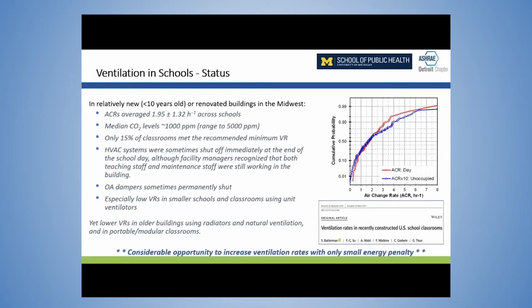So what's the status of ventilation rates in schools in Michigan and the Midwest? We did a study, looked at about 40 different schools, a bunch of classrooms in each one. The condition that we found was not great. This was done prior to COVID, about 5 years ago, but in new schools, less than 10 years old, or newly, fully renovated schools, the air change rates averaged just under 2 air changes per hour. We want 3. Only 15% made it to 3. You can use CO2 as an indicator, easy to measure, of ventilation rates. We have several papers that describe how to do that effectively.